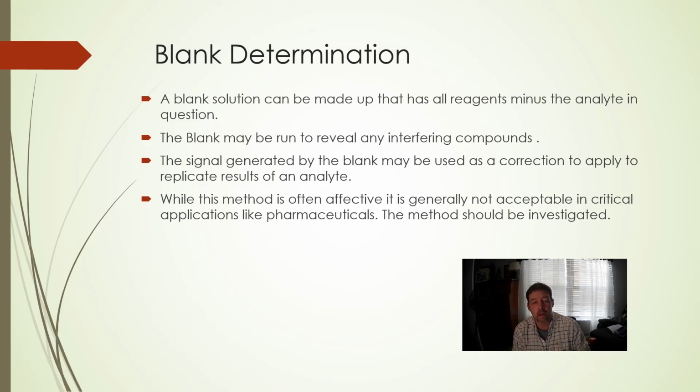What I'm saying here is that you suspect that the instrument is off by about 3%. You make up a sample with none of the analyte you're trying to analyze, just a blank, the reagents, what it's dissolved in, and whatever buffers you're using, and you run that through and you get your signal. And we'll get into signal to noise ratio at one point down the line too. But you can use that and say, hey, look, we are off by 3%. This method is effective sometimes, but it's not acceptable in critical applications, especially pharmaceuticals.